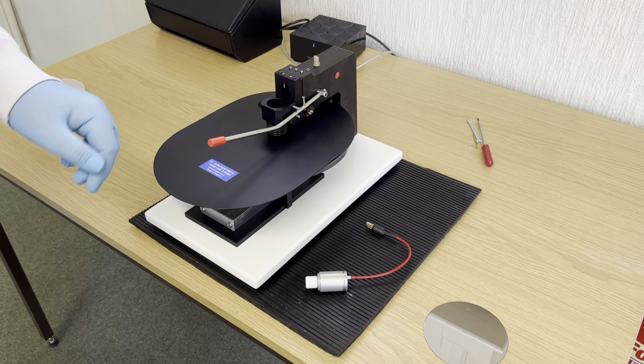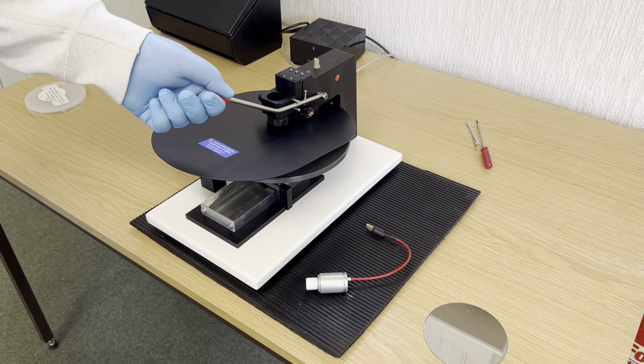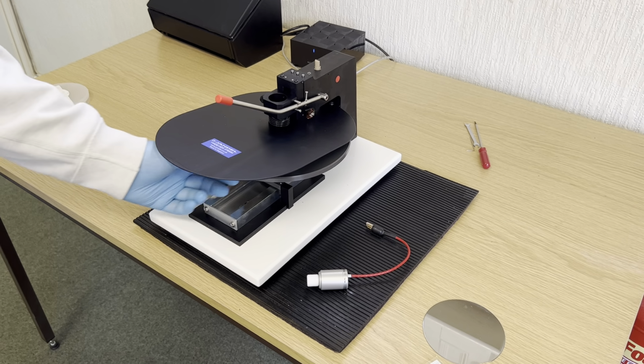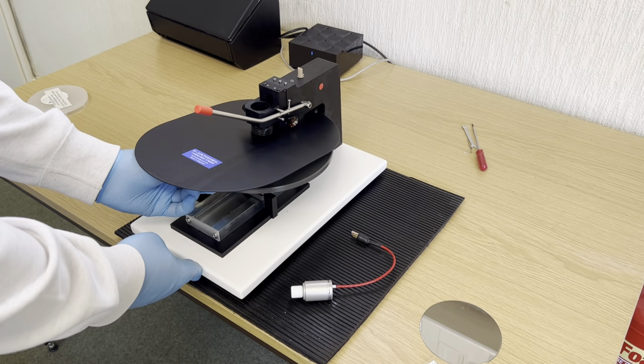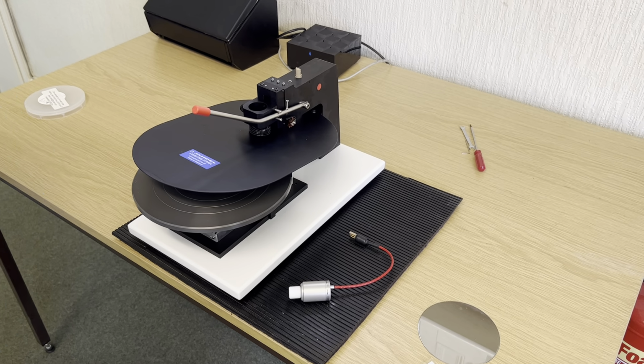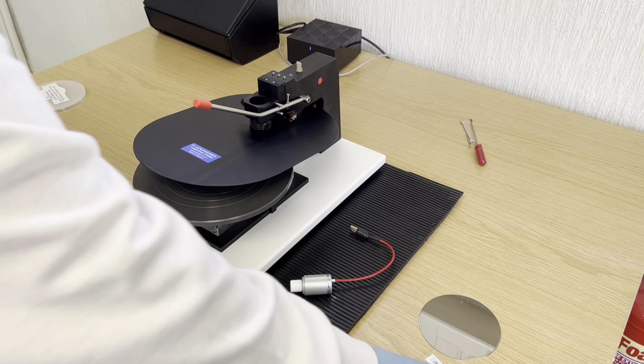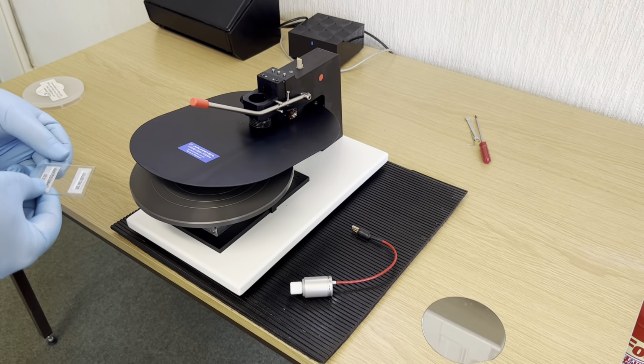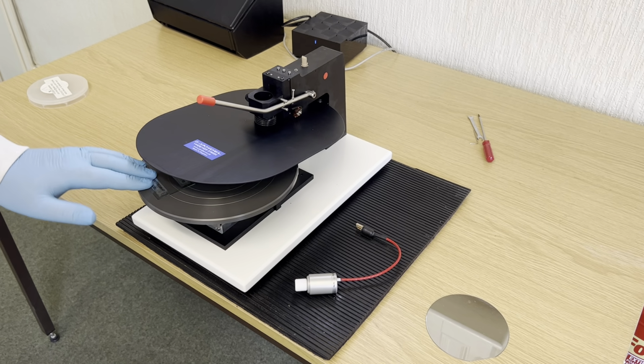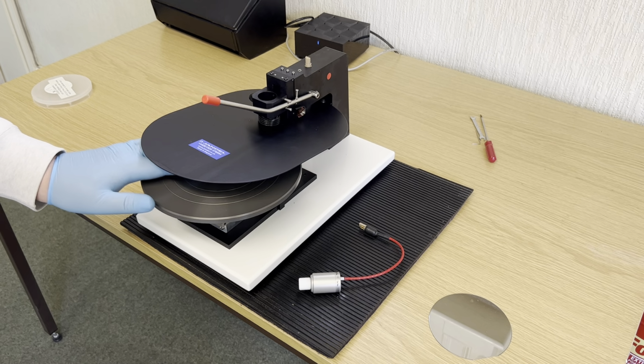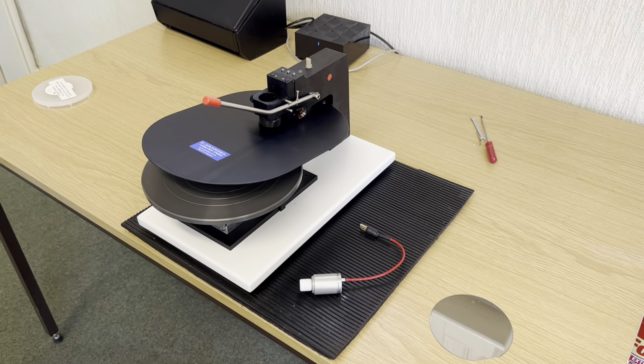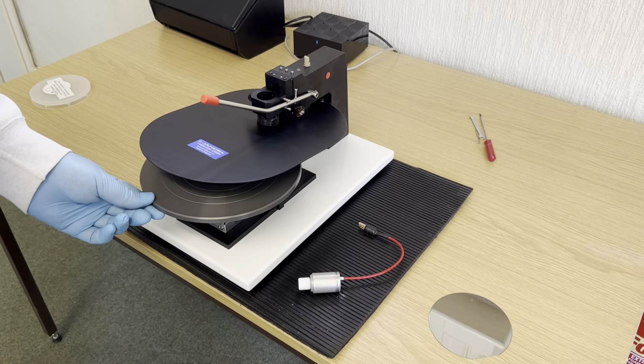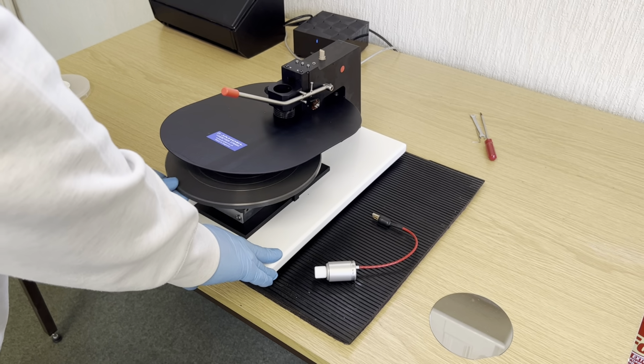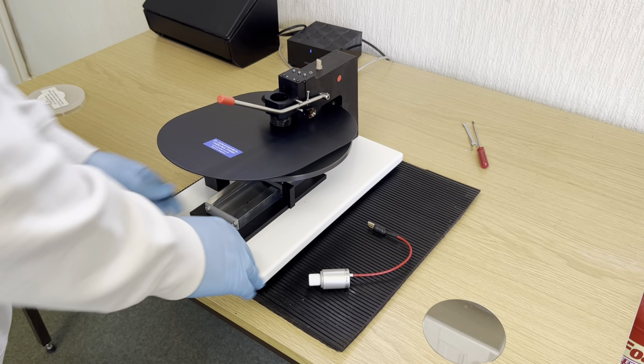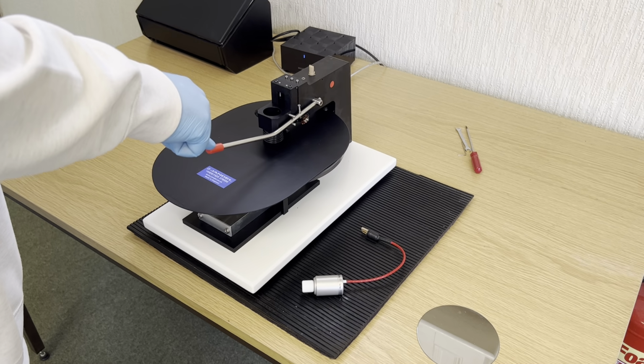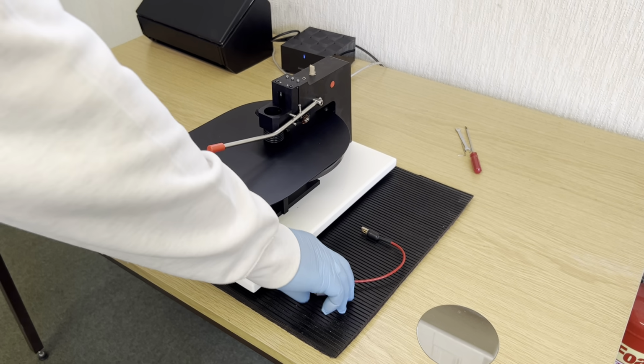To set up the probe head, we're going to start with the probe holder raised and the table out at its furthest position. Here we've got a typical reference sample which we'll place over the centre hole in the table, which is the centre of the measurement. We're then going to push the table all the way in and lower the probe holder as far as it goes.